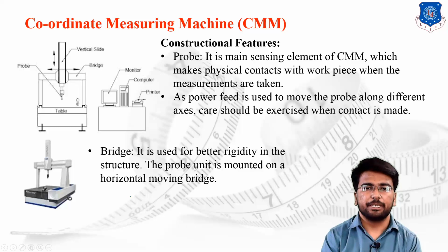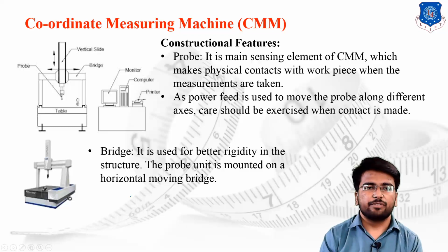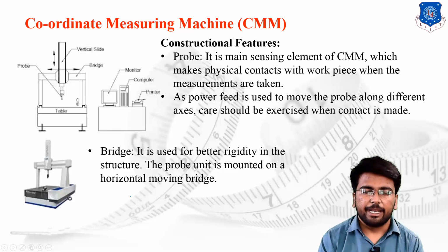And what is a bridge? The bridge is used for better rigidity of the structure, and the probe unit is mounted over the horizontal moving bridge, as we have discussed. So by using the bridge and the vertical slide, we can cover all three mutually orthogonal directions, and by the directional motion of the probe, we can cover the cuboidal shape of the given table.